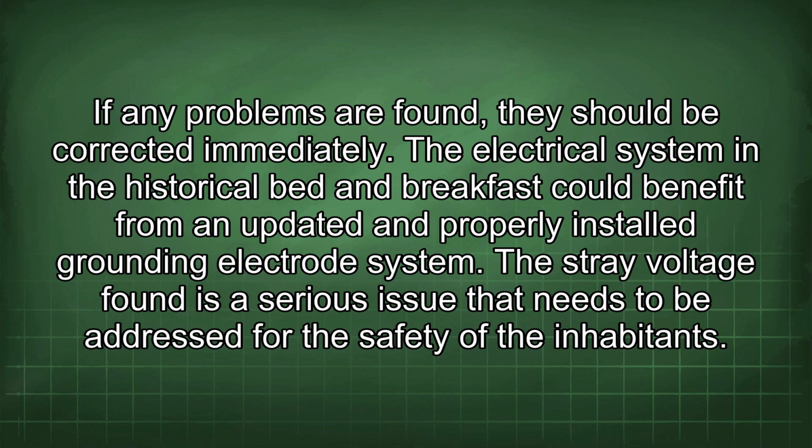The electrical system in the historical bed and breakfast could benefit from an updated and properly installed grounding electrode system. The stray voltage found is a serious issue that needs to be addressed for the safety of the inhabitants.